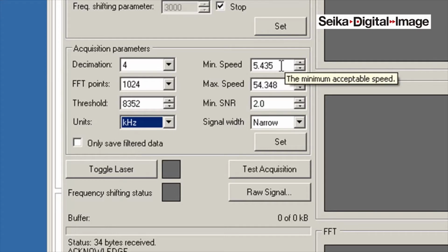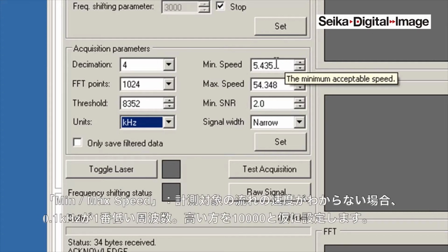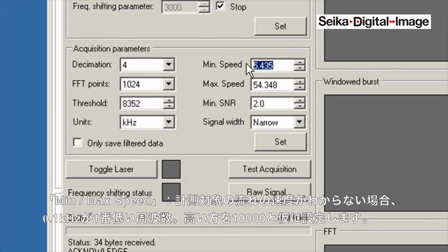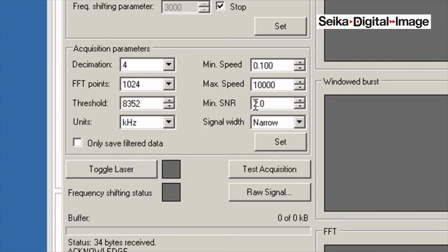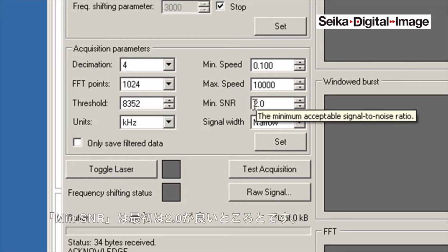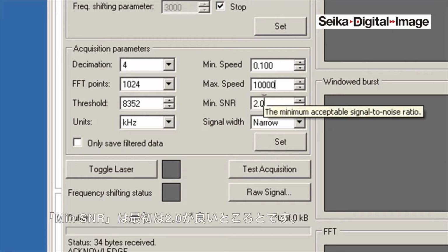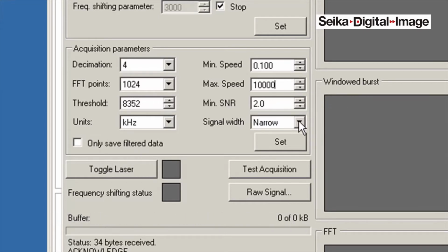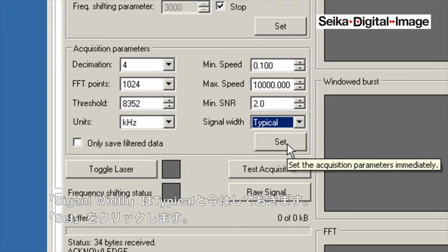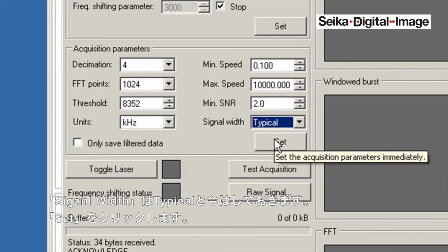For the flow, you need to understand what the speed of your flow is. But since you have no idea, you can start by putting 0.1 kilohertz as your lower frequency, and maybe 10,000 or 10 megahertz for the higher frequency. Minimum SNR of 2 is a good starting point. You can change it as you learn more, but to get started, 2 would be fine. And the signal width is typical. I'll explain to you later. And you push set here.